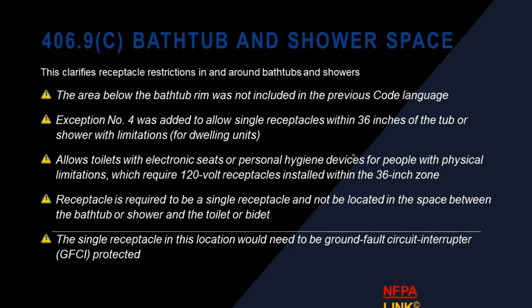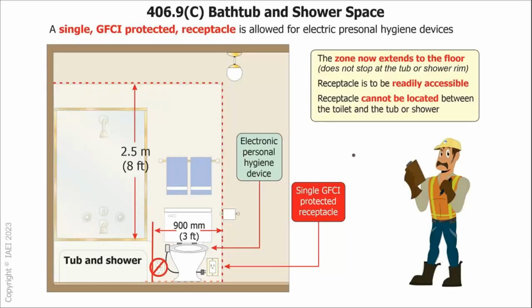Another code change, and it's actually a pretty significant positive thing, is 406.9: bathtub and shower space has been clarified. So in the previous code, it didn't mention anything below the rim of the bathtub. So I could literally put an outlet just below the bathtub water level, 2 inches away, and it was totally okay. They've cleaned up the language so that now there's an entire bathtub and shower space that's been identified, and that's 3 feet by 8 feet. There's some exceptions about when you can add an outlet. You could do a single GFCI protected outlet for a bidet or something of that nature.